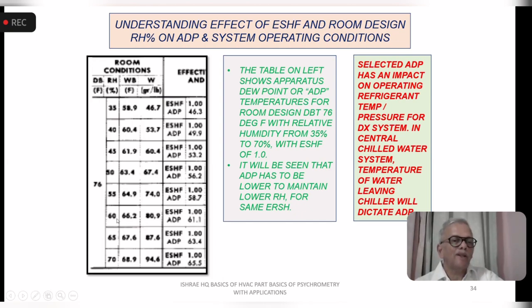But if you want to maintain the humidity at 40%, you will have to operate the apparatus at 49.9 degrees Fahrenheit. You see, from 61.1 to 49.9 is almost 11 degrees difference, which means for the system where you want the lower humidity to be maintained, you'll have to operate the system apparatus at a lower temperature.